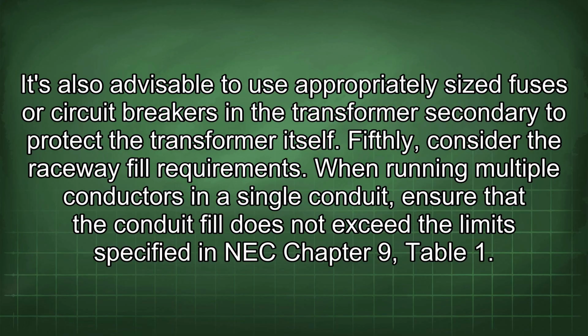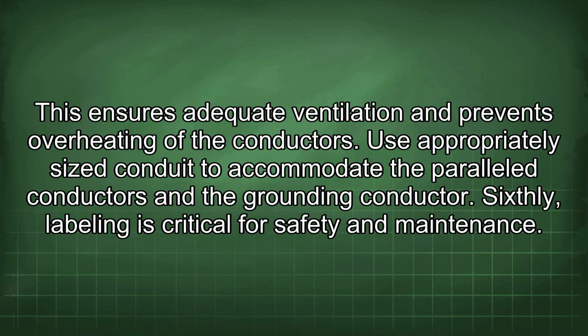Fifthly, consider the raceway fill requirements. When running multiple conductors in a single conduit, ensure that the conduit fill does not exceed the limits specified in NEC Chapter 9 Table 1. This ensures adequate ventilation and prevents overheating of the conductors. Use appropriately sized conduit to accommodate the paralleled conductors and the grounding conductor. Sixthly, labeling is critical for safety and maintenance.